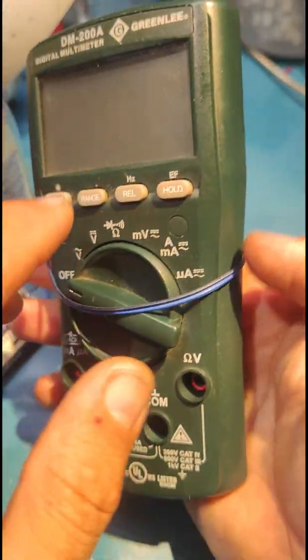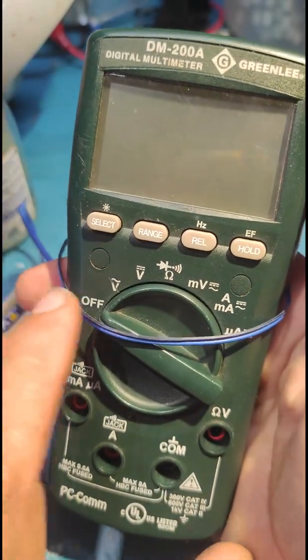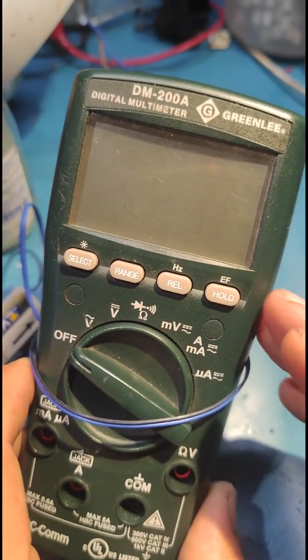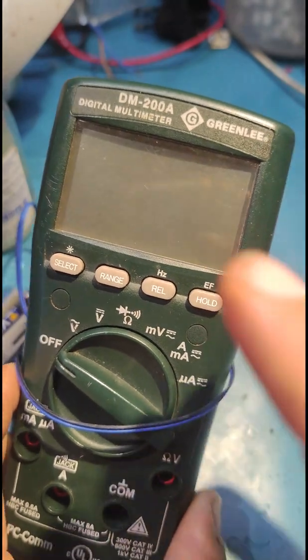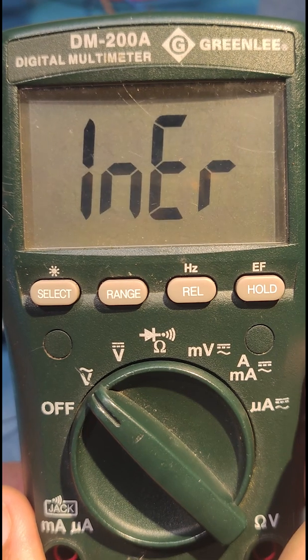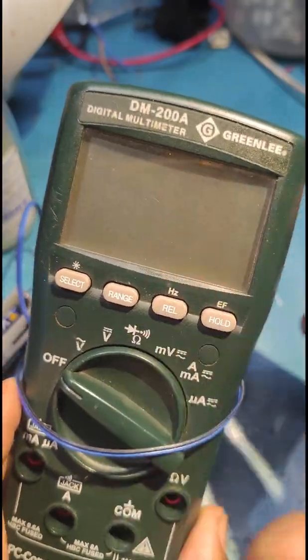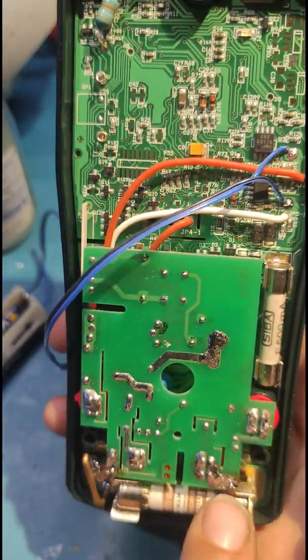Hello, today on the bench I have this multimeter, which is a DM-200A made by Greenlee. It is not a standard electronic multimeter — you find it mainly for industrial purposes. The problem with this is you can get an error message on the display, which reads 'inn' for internal and 'err' for error. This internal error comes from a very sophisticated plug on this multimeter.